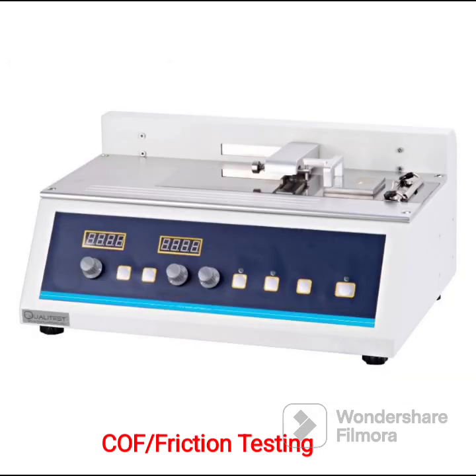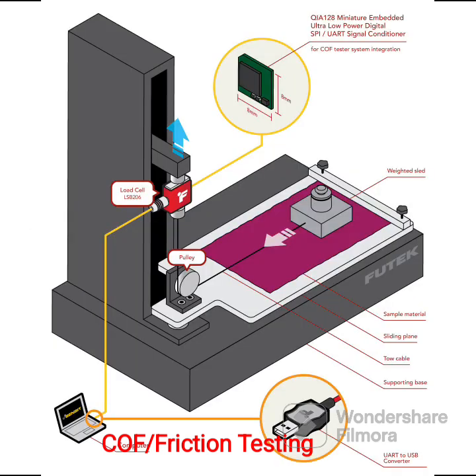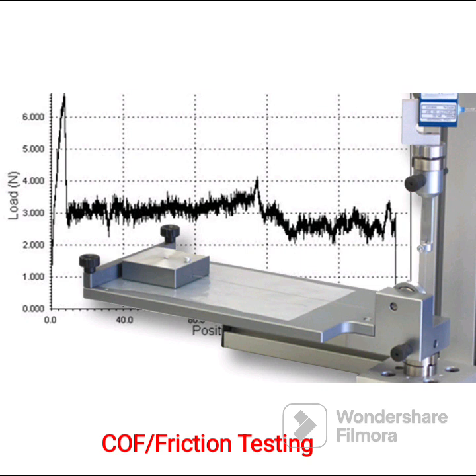Friction testing. A friction tester, also called a coefficient of friction (COF) tester, makes a measurement of a sheet-like substrate such as paper, corrugated, plastic film, or paperboard, which determines the angle of inclination at which one substrate affixed to a sled will begin to slide or slip against the surface of another substrate of a similar material.